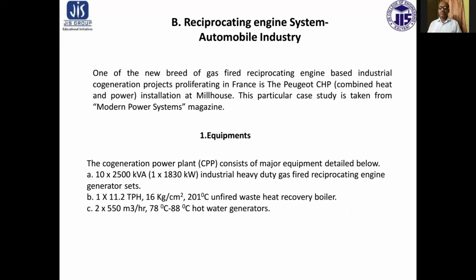The equipments, this cogeneration plant consists of major equipments details below. That is one 1830 kilowatt industrial heavy duty gas fired reciprocating engine generator set, 11.2 TPH 16 bar 201 degree centigrade unfired waste heat recovery boiler, and two numbers of 550 meter cube per hour 78 to 88 degree centigrade hot water generators.